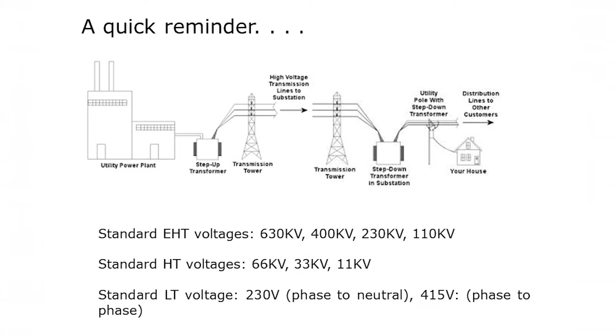A quick reminder, especially for Omar: in electricity, power P equals voltage multiplied by current, P is V into I. So a given quantity of electricity can be transferred from A to B either with high voltage and low current, or high current and low voltage. Typically for transmission over long distances you use higher voltage and lower current, because high current means bigger conductors, and losses in a cable are I squared times resistance - so double the current means four times the losses. That's why transmission lines are 230 kilovolts, 110, 400, then 33/11 distribution, and finally 230 volts at your plug.